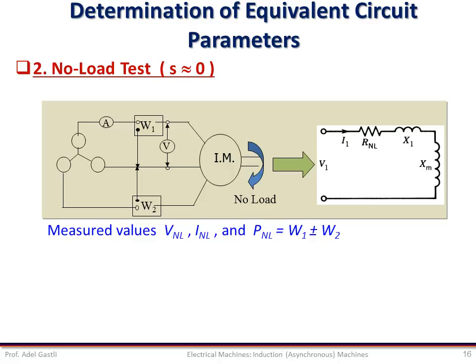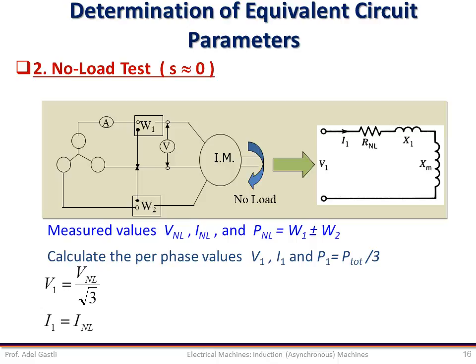The no-load power P_NL represents the total losses, including the stator copper loss and rotational loss, which also includes core and mechanical loss. From the measured line-to-line no-load voltage VNL, we can deduce the equivalent circuit phase voltage V1. The stator phase current is the same as the line current. The rotational loss can then be calculated accordingly. The equivalent no-load impedance is Z_NL = V1/I1, and the no-load equivalent resistance R_NL is determined as P1/I1².